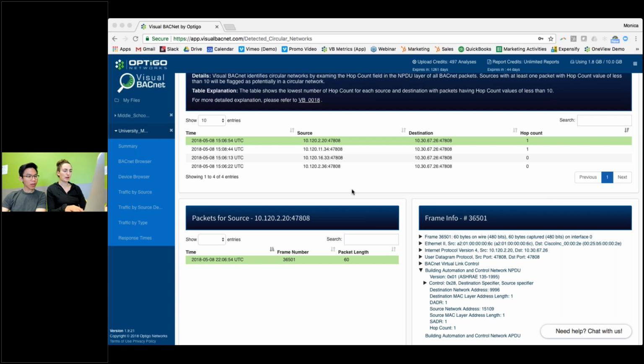All right. So there's a potential here which happens in BACnet IP and BACnet Ethernet. It's very easy to turn both protocols on typically in many BACnet systems, as simple as a checkbox. So it could be a case of what's happening here, or it's possible that if there's multiple network cards on there, then somehow they're routing together. So that would be interesting to dig into for a bit more information.